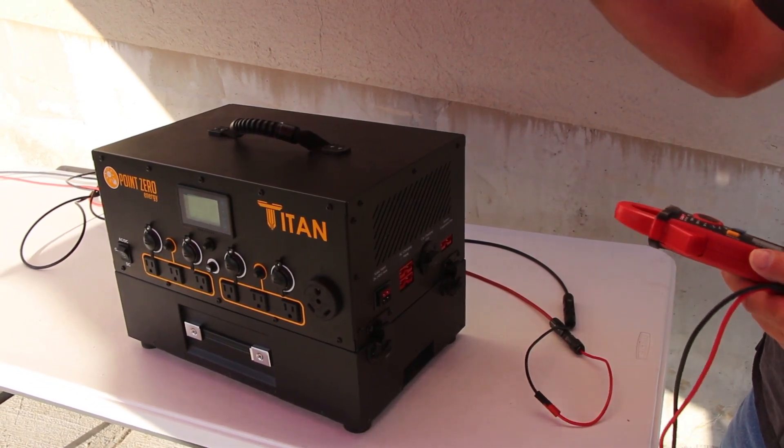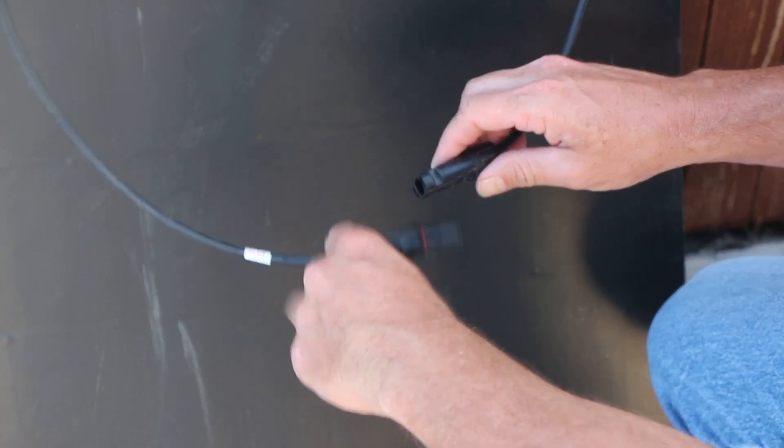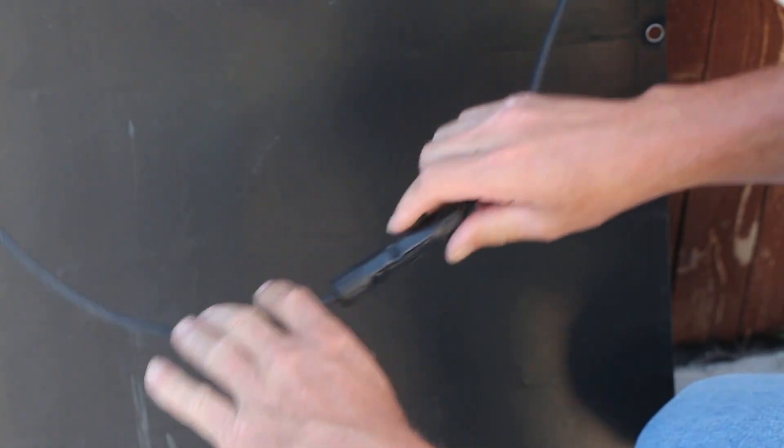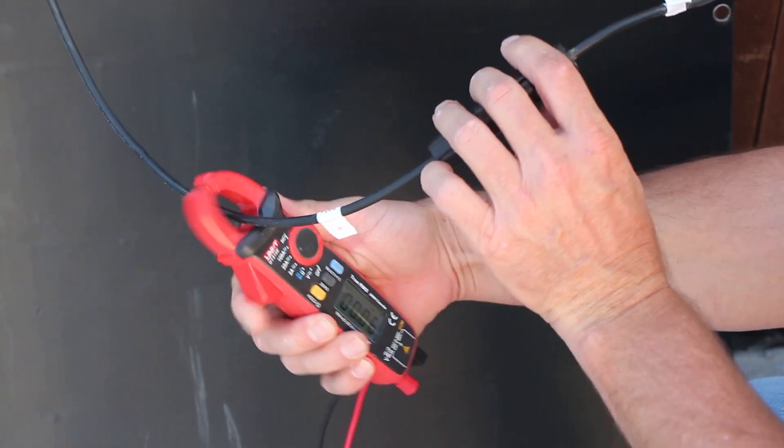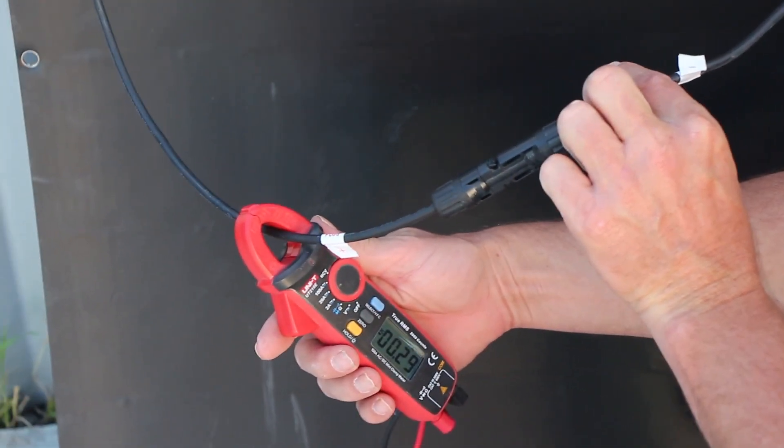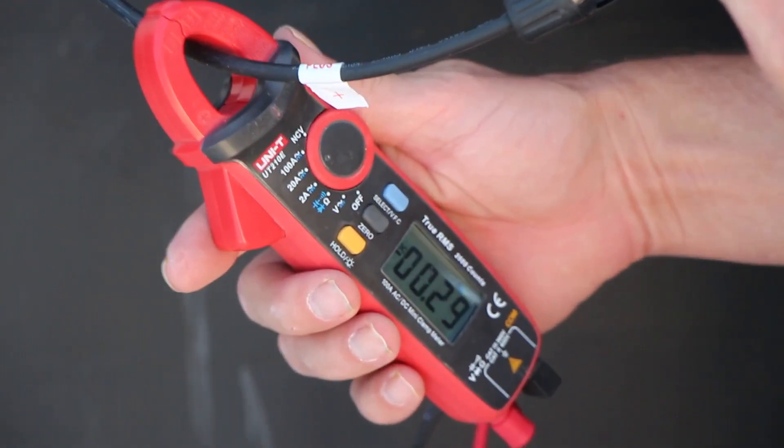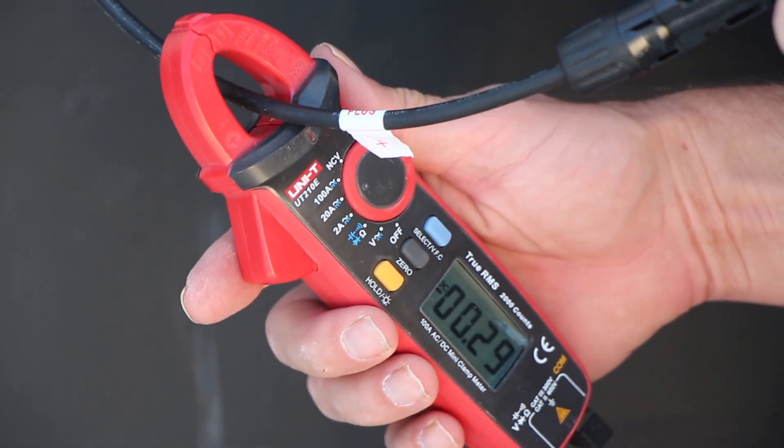You can troubleshoot and you can actually go to each solar panel, short circuit, plug both of the panel's wires together and measure its current, measure its voltage. And you can test every single solar panel individually and see if you find one that is weaker or not working correctly.